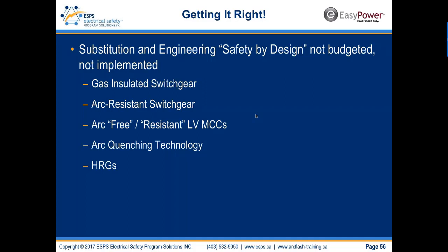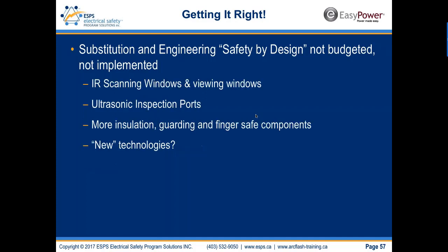There's a lot of good coming out of this. The studies are driving a lot of this as well. So the upside of the studies is not only the equipment labels with the arc flash and shock data, but new equipment or upgraded equipment being installed. Scanning windows and viewing windows are being installed. We're seeing ultrasonic inspection ports being installed. Companies are hopefully, and I've seen it, specifying more insulation, more guarding, and more finger-safe components, and new technologies are evolving. So there's lots of good stuff happening.